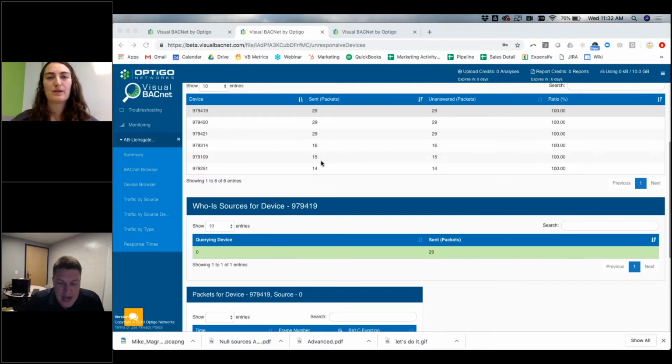One of the comments was that the diag with full bars all the way up to the top was not a good sign in ALC's world. Right. Yeah, I would say based on what we've heard from a lot of customers, one of the most challenging scenarios to troubleshoot is bad wiring, because inevitably you're not getting all the data and you're not getting all the communications. Bad configurations we can usually figure out. Bad wiring is a tougher one to deal with and a tougher one to fix as well, because you just have to go and yank on wires.